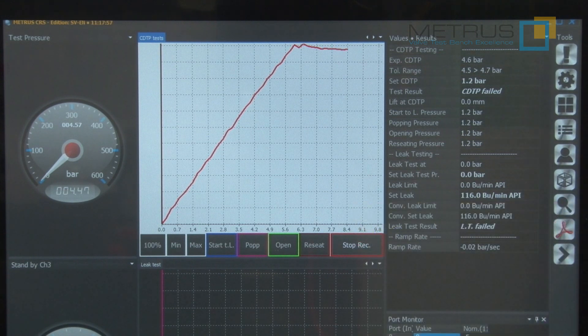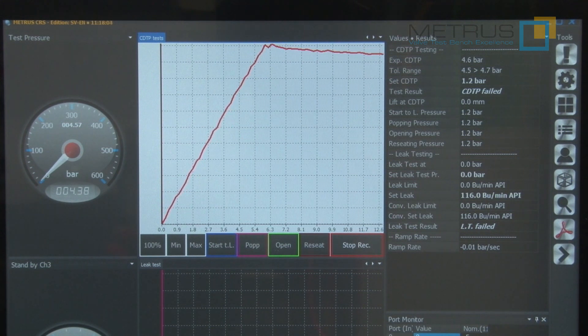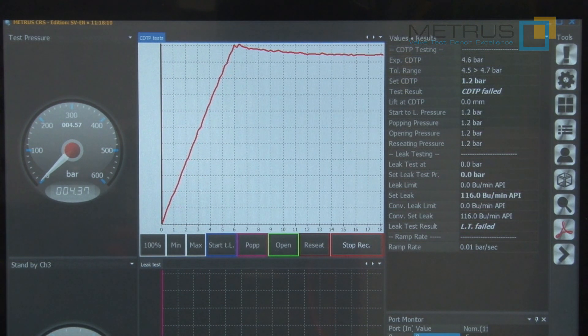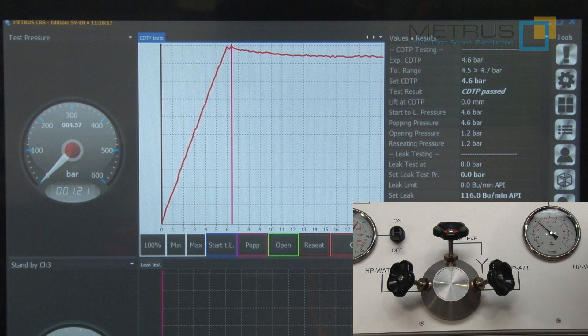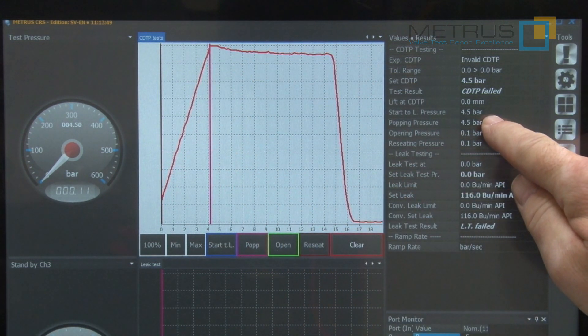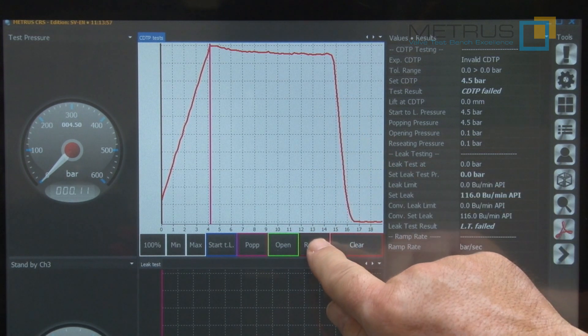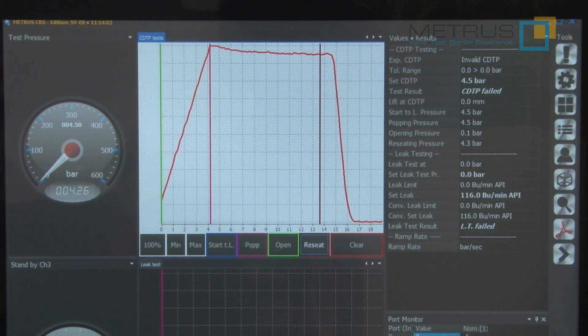As soon as I have reached the popping pressure, I wait until the pressure will not drop anymore. This is my reseating pressure, and I open now the needle valve for releasing the pressure and the measurement will stop. The system shows me automatically the pop pressure, which is at approximately 4.5 bar. If you would like to also define the reseating pressure, just push here on reseat, place the cursor at the end of the graph, and the reseating pressure will also be shown in your test certificate.